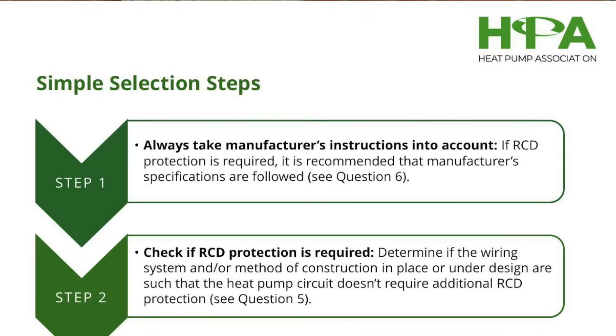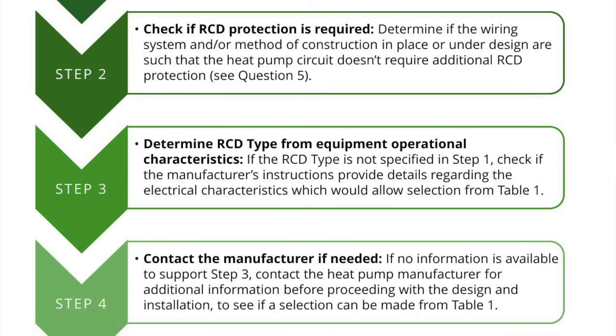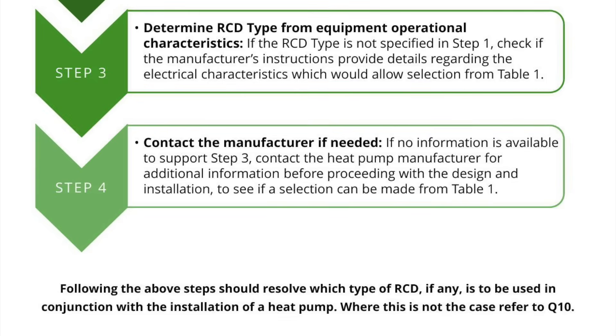Step 1: always check the manufacturer's instructions. If an RCD is required, the manufacturer will typically specify the type of RCD to use. Step 2: determine if RCD protection is necessary — not every heat pump circuit requires additional protection, particularly if the wiring system is designed with mechanical protection. Step 3: if no information is available from the manufacturer, refer to the heat pump's operational characteristics; these details will help you select the correct RCD type. Step 4: if you're still unsure, reach out to the manufacturer directly for more guidance on selecting the right RCD.